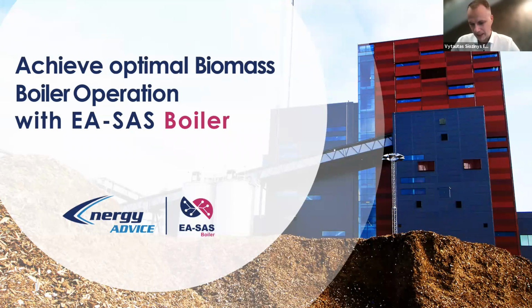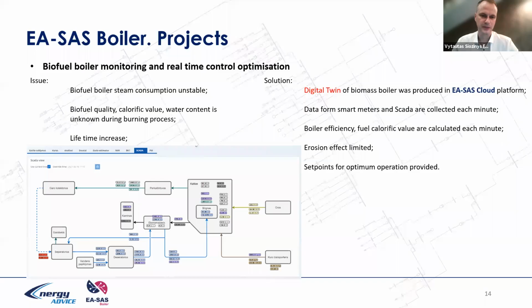Next, on the same platform, we put a digital twin of a biomass boiler. I mean a digital twin where we run biomass burning equations and a thermal model of the boiler, and run these calculations every 5 minutes. And we are capable of monitoring the fuel efficiency of burning biomass fuel. And here are a couple of examples of this digital twin solution.